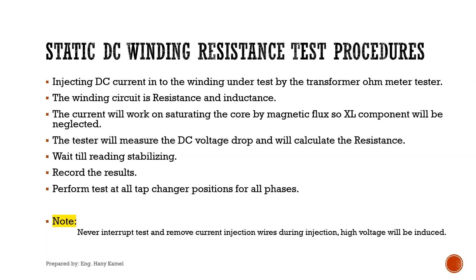Perform the test at all tap changer positions for all phases. Never interrupt the test and remove current injection wires during injection — high voltage will be induced.